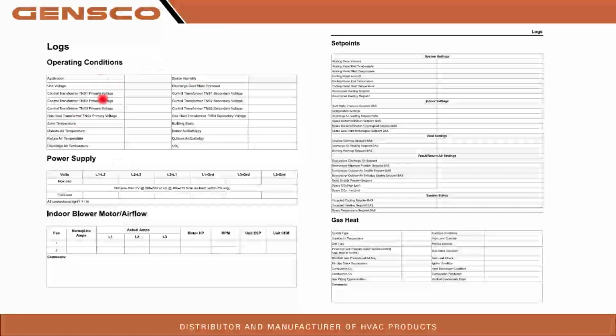Once you know what to input in here, you can take that voltage pretty quick, outside air temperature, and what is your actual control transformer. If we're actually checking our line voltage at startup, we're going to save a lot of callbacks, right? So we're going to confirm that we actually have a good power supply. And if the building does get hit with some kind of power surge and they have to repair it, and we can verify, hey, look, this was our line voltage at startup, what happened to the building? Now we can charge within that year for coming back to the building instead of giving them a free service call.